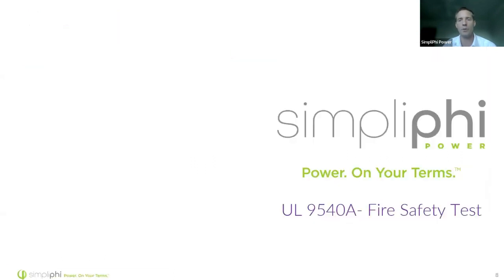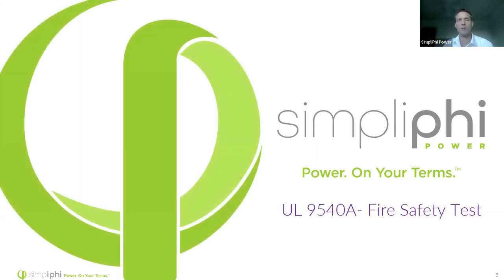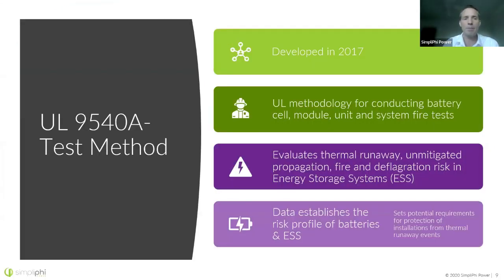We're going to start off with the test: UL 9540A, a fire safety test. We're going to force these batteries into thermal runaway and catch fire, and monitor the conditions to make sure they're safe. This UL 9540A test method was developed in 2017.